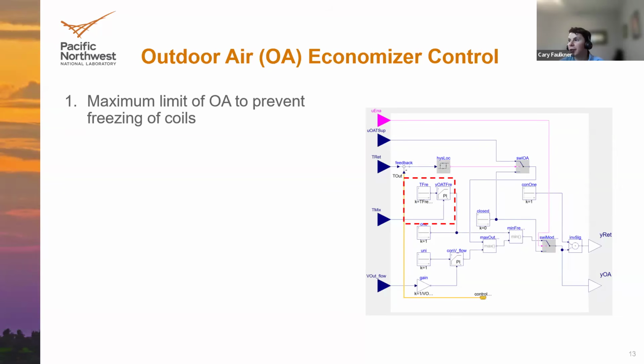to freeze the coils. I should mention, a common theme in these controls within Modelica is having these PI blocks, which are connected to some sort of sensor measurement and then the desired set point, and then it's going to feed that PI signal downstream to some sort of actuation. And so that's what you'll see a lot here: these PI blocks connected to measured inputs or set points.